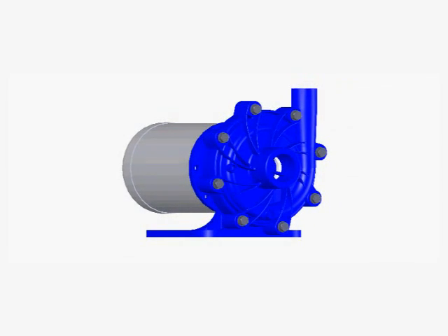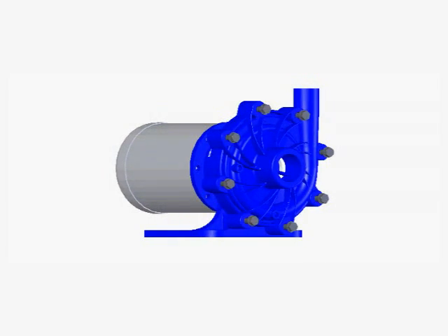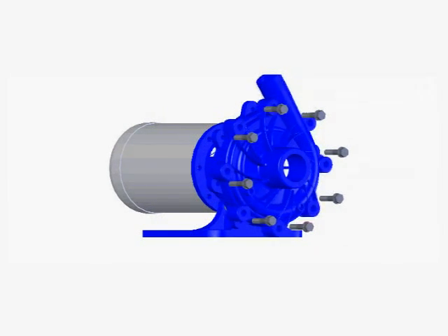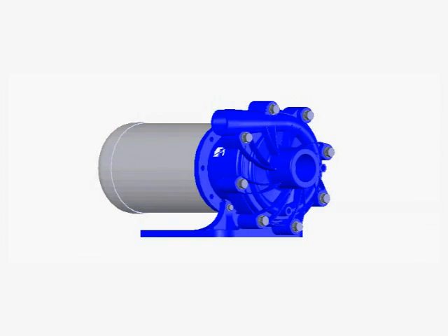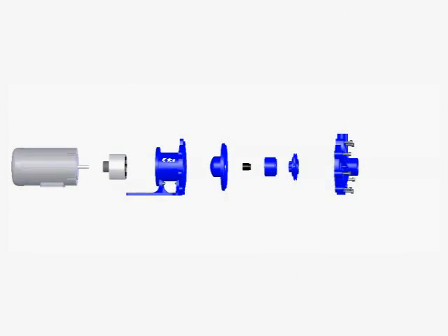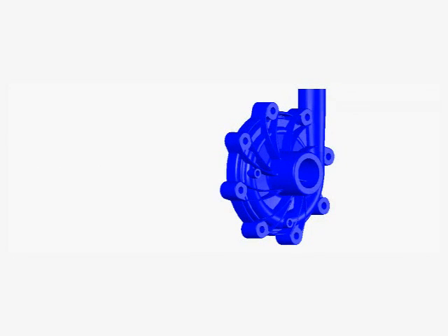Casing drains molded in two locations enable the pump discharge to be positioned vertically or horizontally. Careful attention to detail is apparent in every component of the DB series. The unique design of the casing produces equivalent performance at both 50 and 60 Hertz operation. Evenly spaced impeller trims make the DB series a perfect solution for any hydraulic rating.